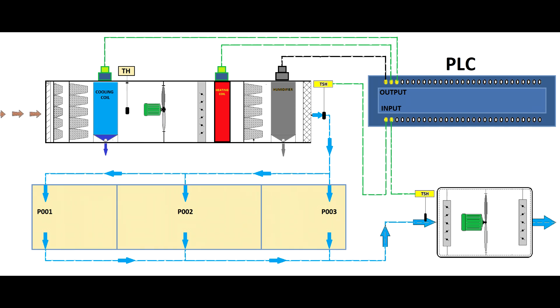As you will see in this video, the cooling heat exchanger and the heating heat exchangers run together at the same time. And you say, 'Whoa, why would I need to cool the air and then to heat the air again? I don't understand.' Well my dear friends, sometimes when you want to dehumidify the air, you have to run the cooling heat exchanger, and the cooling heat exchanger will cool the air. And you might not need the air to be cold, so you have to reheat it to keep the air temperature constant. So please remember, when you dehumidify the air, sometimes the temperature drops and you have to run the heating heat exchanger to keep the temperature constant.